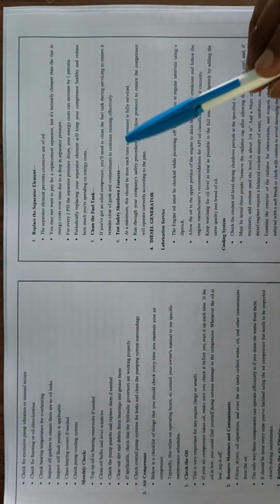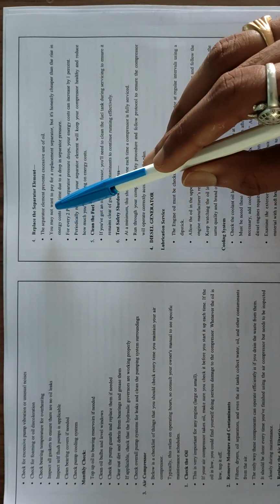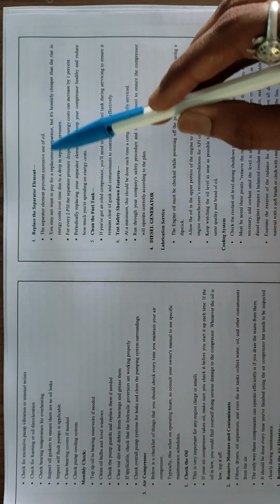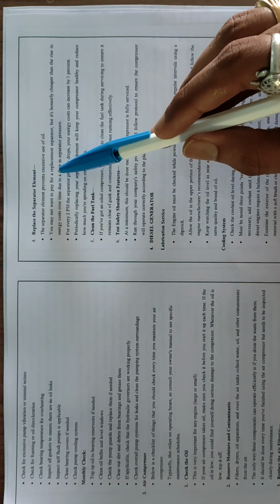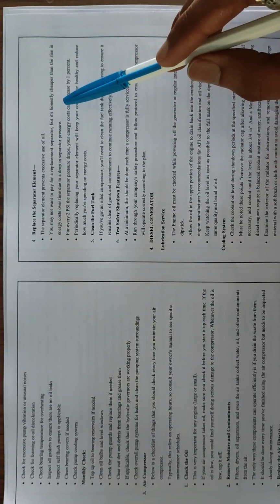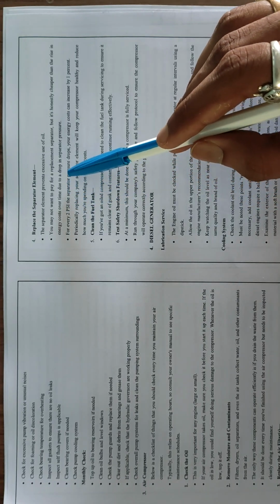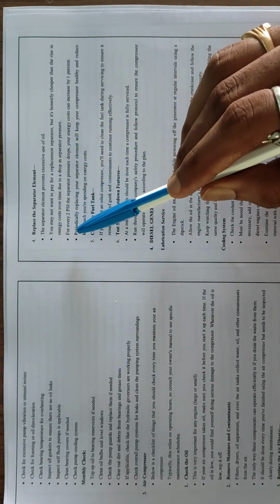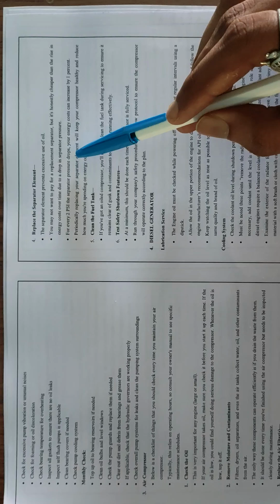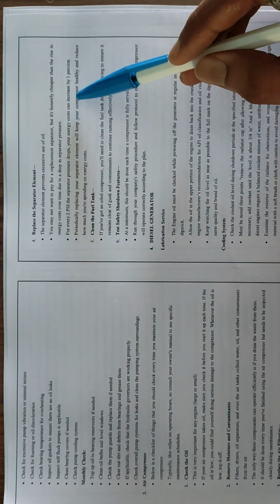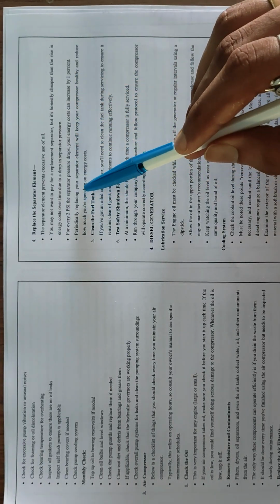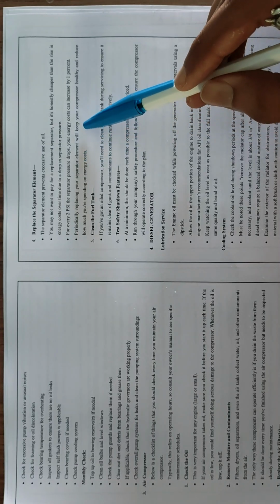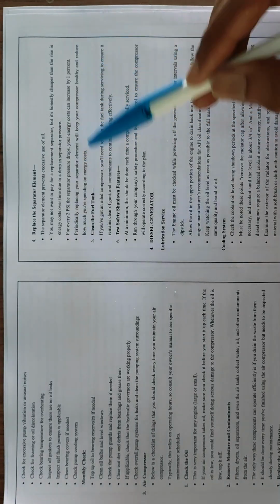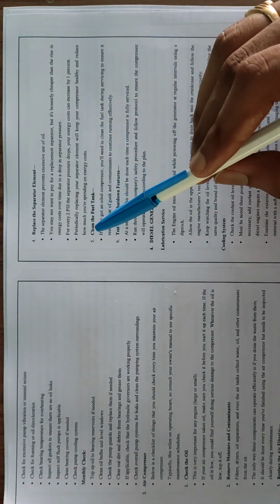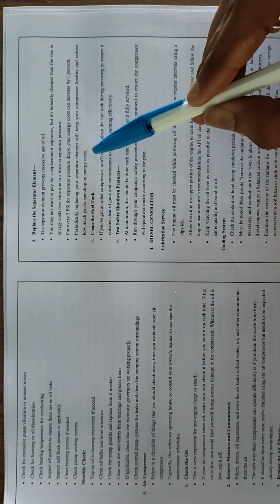Replace the separator element. The separator element prevents excessive use of oil. You may not want to pay for a replacement separator, but it's honestly cheaper than the rise in energy cost over time due to a drop in separator pressure. For every 2 psi the separator pressure drops, your energy cost can increase by 1%. Periodically replacing your separator element will keep your compressor healthy and reduce how much you are spending on energy cost.